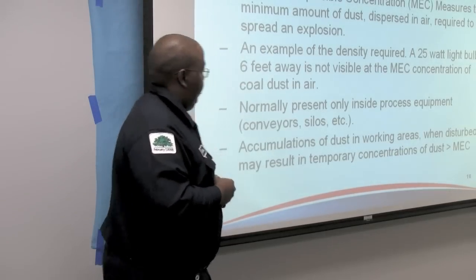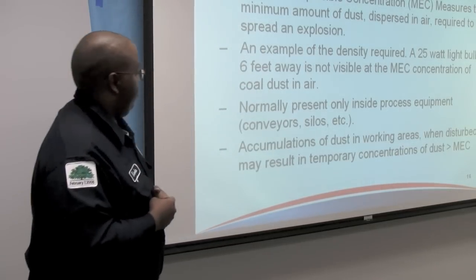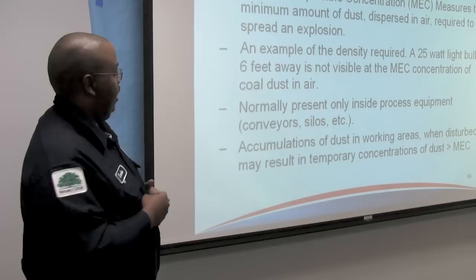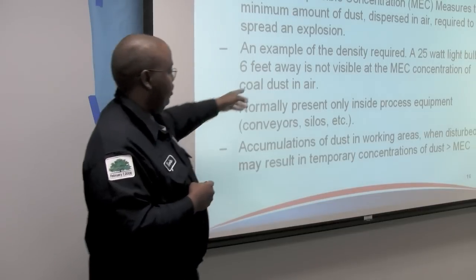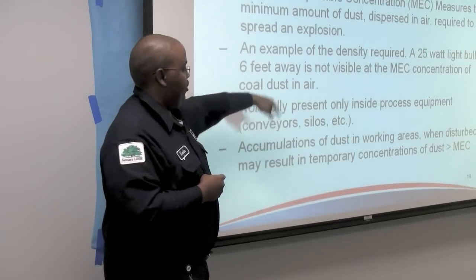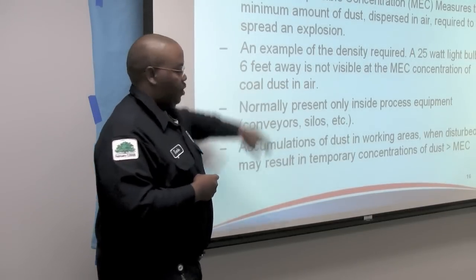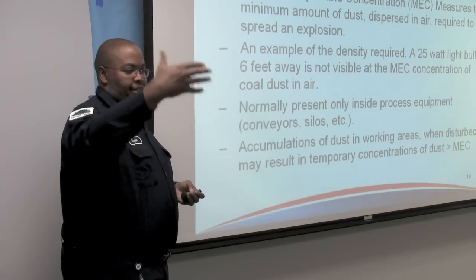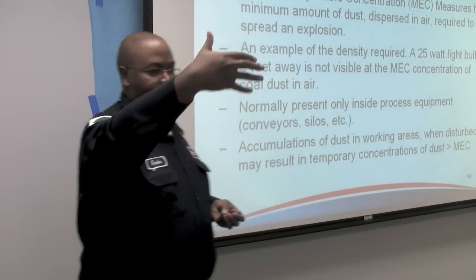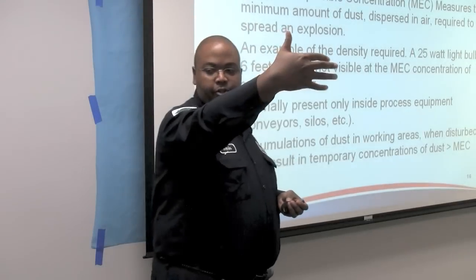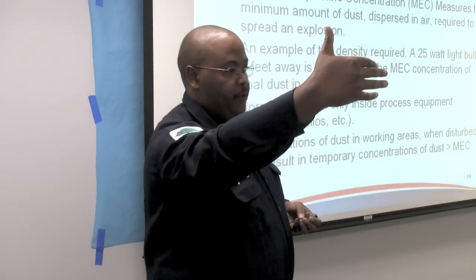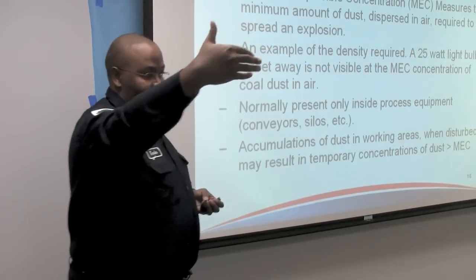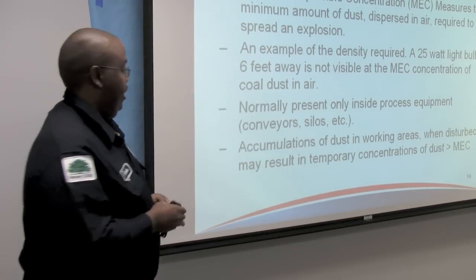Here's an example I've used in training: a 25-watt light bulb six feet away is not visible at the MEC for coal dust. Generally, if you cannot make out the features of your hand at arm's length in front of your face, you are at that minimum explosible concentration.